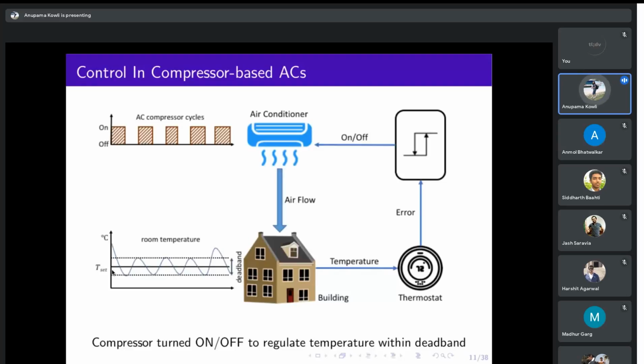It's just a basic bang-bang control. That is what I've tried to show here also. A typical bang-bang control, it's a hysteresis sort of control. You've given it a set point. In and around the dead band set around this set point is where you would try to regulate the temperature, and if you're outside of the dead band, rather above it, is where your compressor is expected to be on. If you're below the dead band or you hit the lower limit of it, then your compressor is going to be turned off. Everybody clear, right?